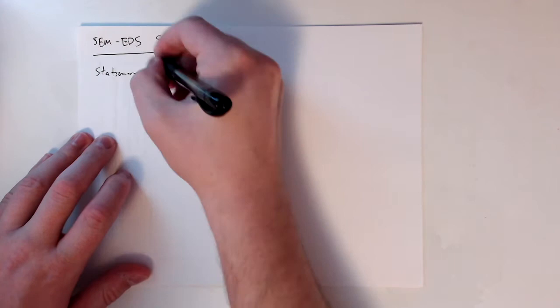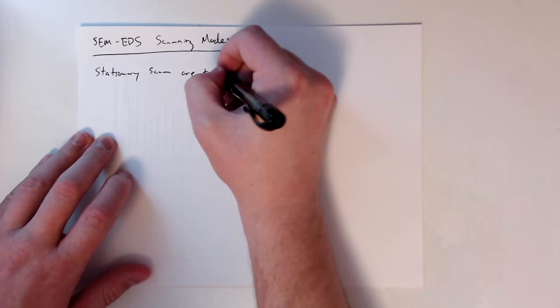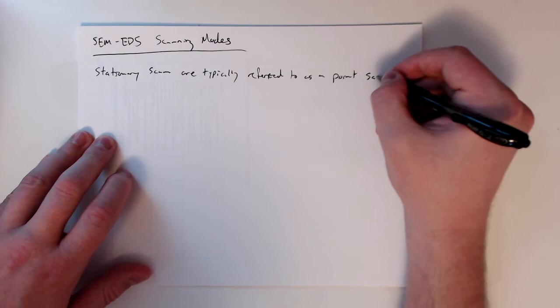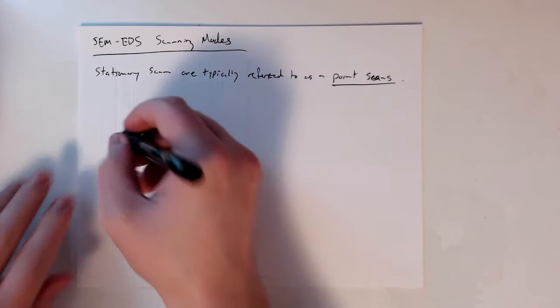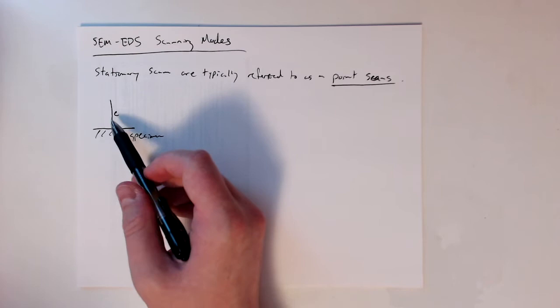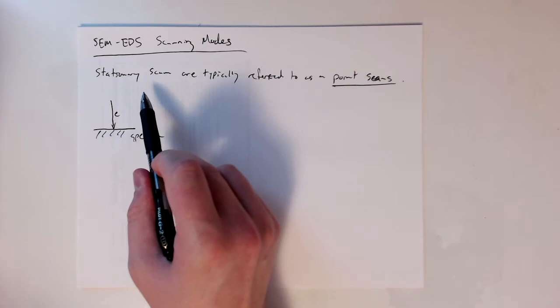If we have what's called a stationary scan, these are also referred to as point scans. Because we have a scanning electron beam in the SEM, so the electron beam hits a specimen. The scanning part of SEM means that this beam can move along the surface. So if we just maintain the beam in one location, then we typically call this a point scan because the electron beam is stationary.